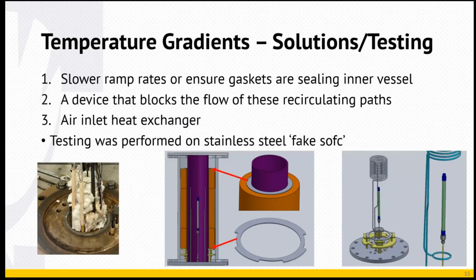We came up with a couple of solutions and ideas. The first, and easiest to test, was slowing down the ramp rates, since we didn't have to change anything other than how we ran the test. While doing this, we also changed out some gaskets to check if we were getting bad sealing between the inner vessel and the top and bottom flanges.